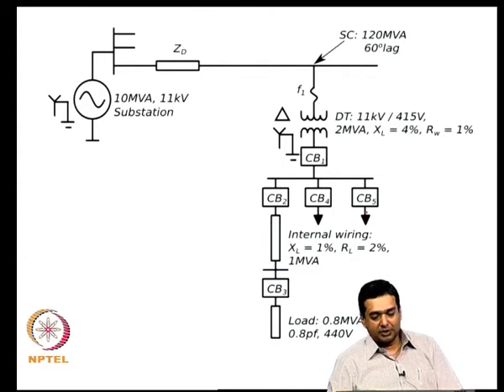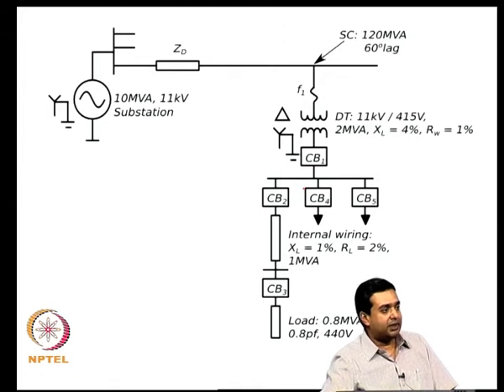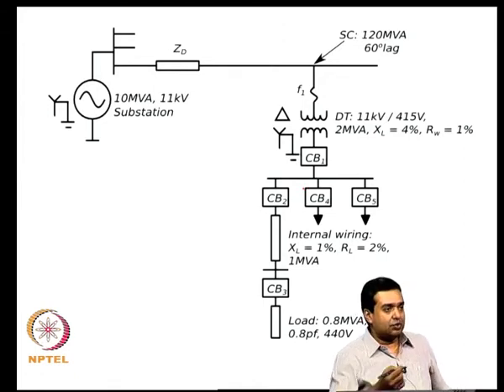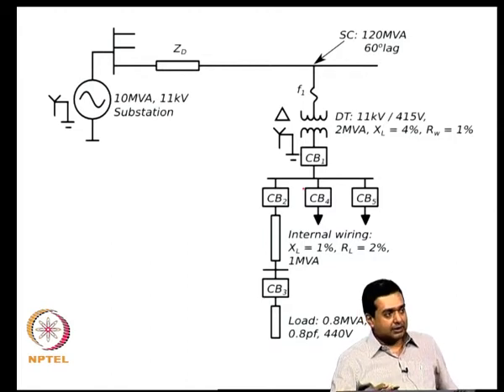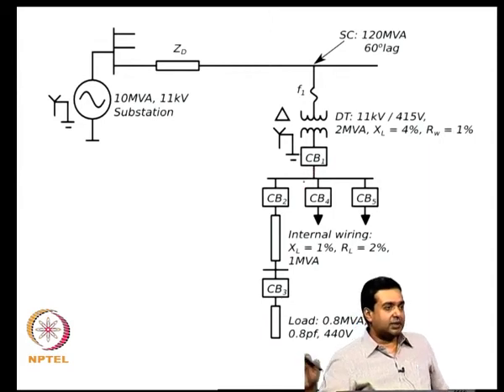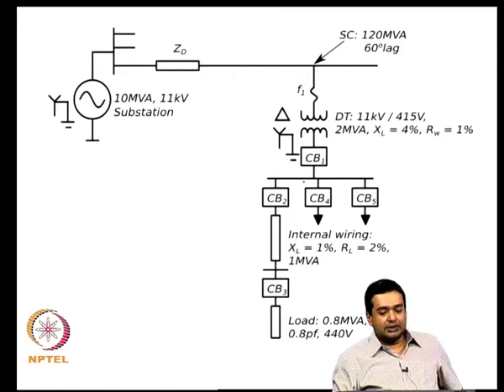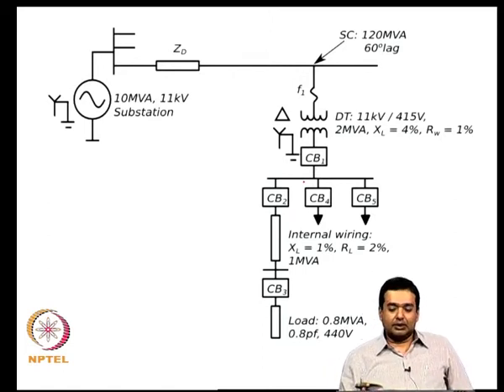Sometimes, people add a series inductance just upstream of the breaker. The purpose of the inductance is to reduce the fault current level. The cost of the inductance may be less than the cost savings on circuit breakers, especially when the incoming feed may go to a large number of branches with many breakers. So you might see wiring inductances being added in some sections to manage fault current to an appropriate level.